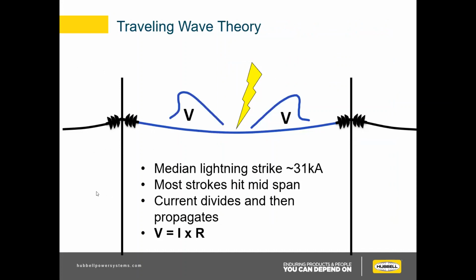So kind of start things off with traveling wave theory. This is kind of what happens when lightning strikes our line, whether it's distribution line or transmission line, it doesn't matter. A median lightning strike is 31 kA. That's just kind of been studied over the years from our ground flash density studies and all things like that. Most strokes hit midspan, and the current will divide and then go in each direction. So we can use Ohm's law, V equals IR, to find out the voltage that your equipment or insulator will see in the event of a lightning strike.